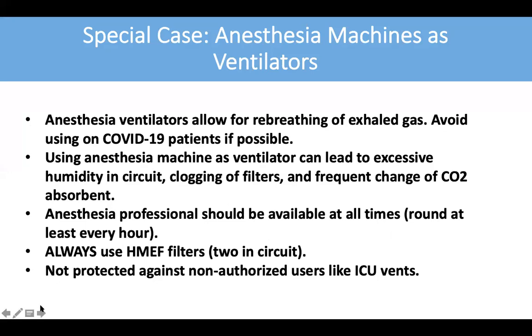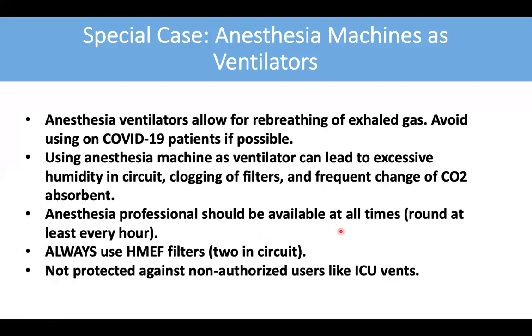Make sure that an anesthesia professional is available at all times and checking in on the machine every hour. Always use 2 filters in the circuit. This way you can reduce the chances of cross-infection. And please note that the anesthesia machine is not protected against non-authorized users like the ICU vents. And so you'll need to reconfigure the alarms to make sure that the alarm volumes are loud enough to get your attention.